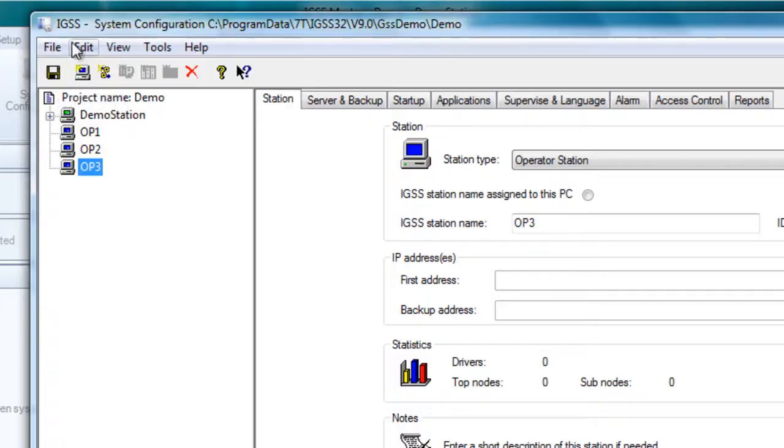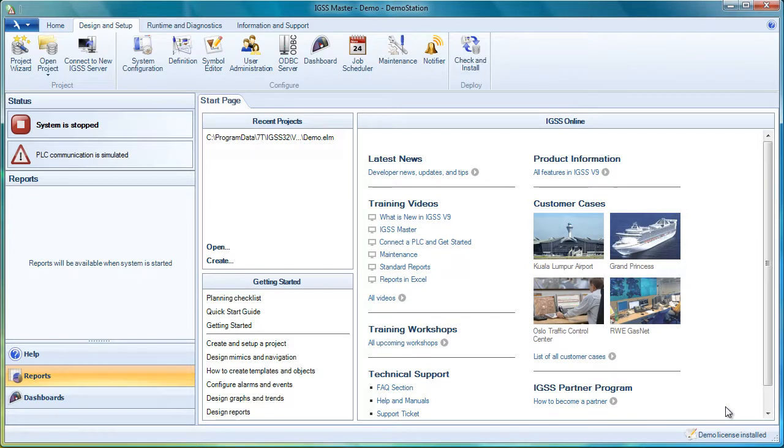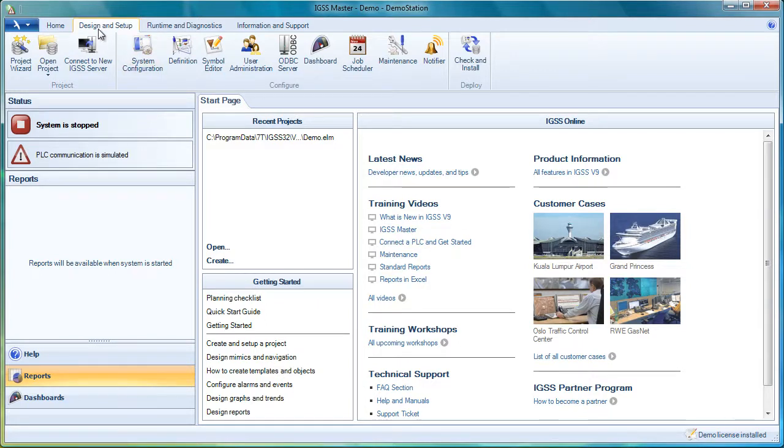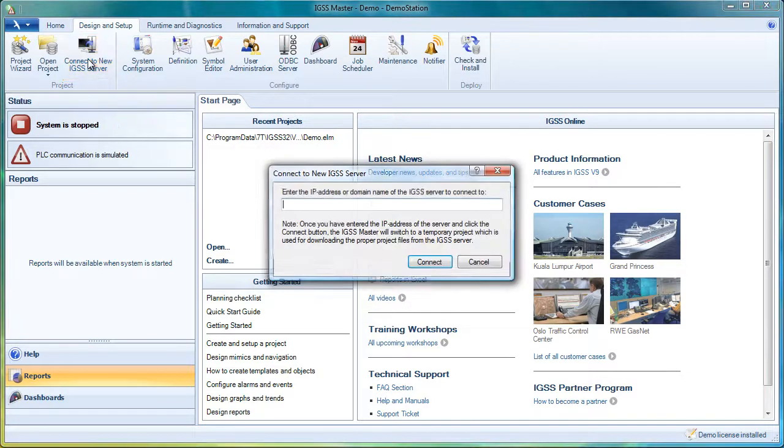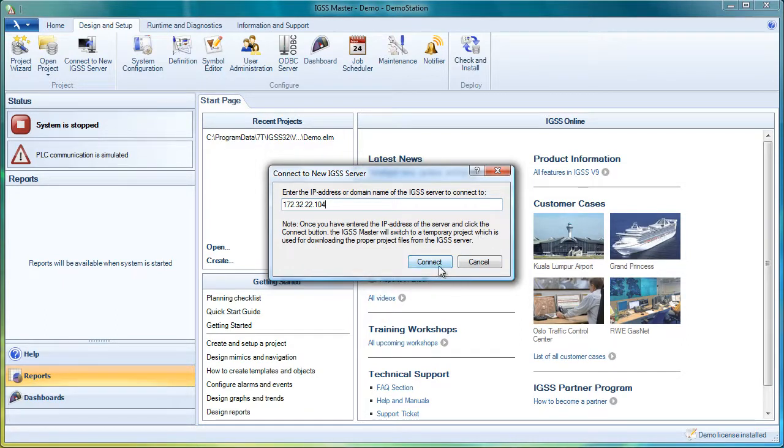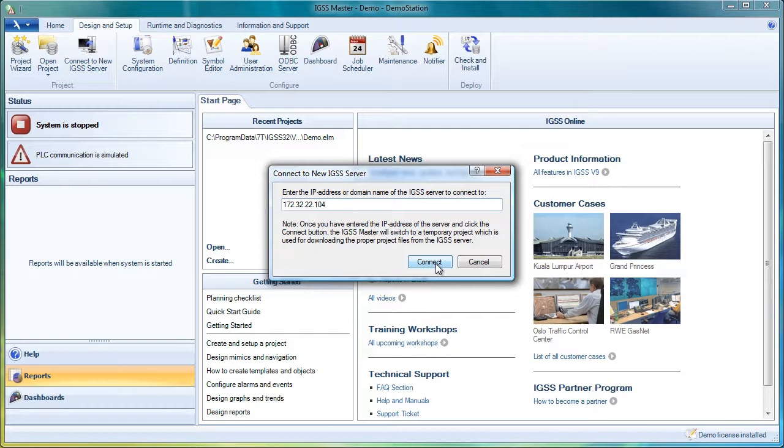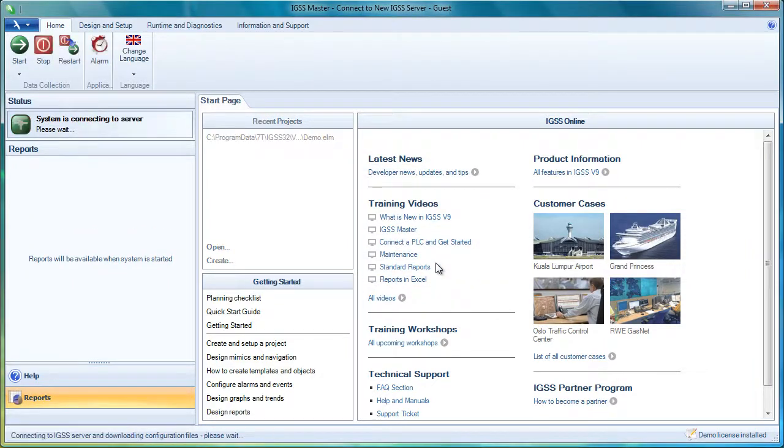So let's imagine that we are on operator station 1, for example. We have created the project. We have run the project on the server. We're ready to link or connect the first operator station. We simply go to the design and setup tab on the operator station. We click on connect to new IGSS server and we enter the IP address, 172.32.22.104, and we click on the connect button. And the new thing here is that it actually creates a temporary project to allow the downloading of the project files and then you're ready to connect the server and the operator station and they will now run together and the operator station will be updated continuously.